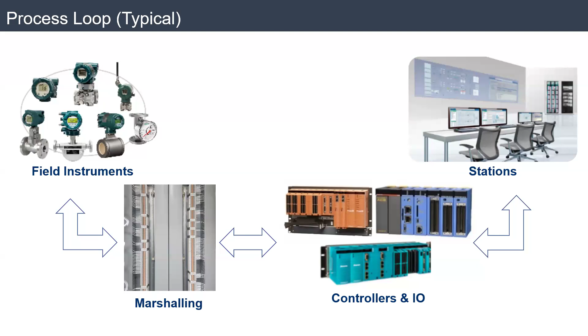Okay, next one. Again, it's just in more depth. Whatever we have seen earlier is a representation of the actual plant. But now, in documentation, how do you present this? As you can see here, field instrument on the left, number one, then the junction box. You have many transmitters, let's say 10 transmitters, and they all come into the junction box. So you have 10 plus 10 cables, 20 cables here. And then from the junction box, you have only one cable going to the marshalling cabinet.